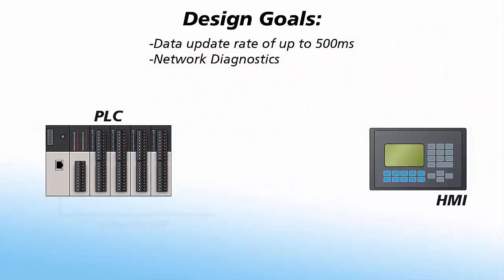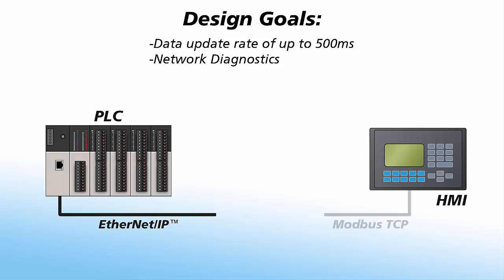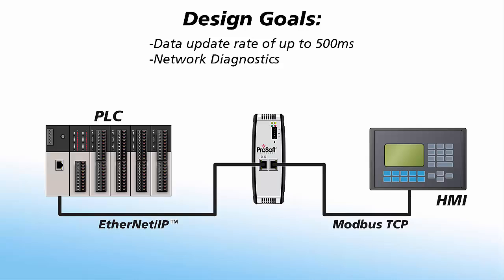We'll begin by taking a look at a PLC that talks EtherNet/IP that needs to communicate with an HMI that talks Modbus TCP. For this example, we'll use a ProSoft gateway to exchange data between the two different protocols. The design goals are to have data communication speeds of no slower than 500 milliseconds and access to the communication diagnostics through the PLC. The HMI is a client, so we'll configure our gateway as a Modbus TCP/IP server. We'll also make the gateway a server on the EtherNet/IP side, meaning we'll need to use message instructions in the PLC program to communicate with our gateway. The client messages from the PLC will be sent with a lower priority, only executing once all the I/O messages have been completed.